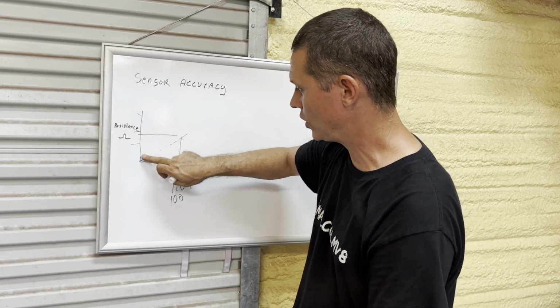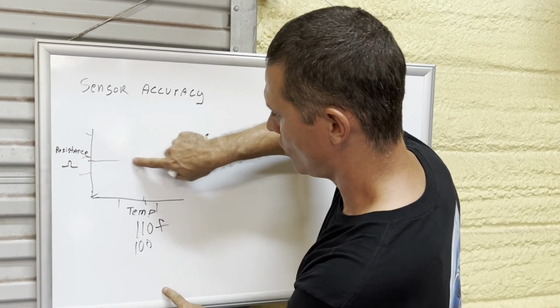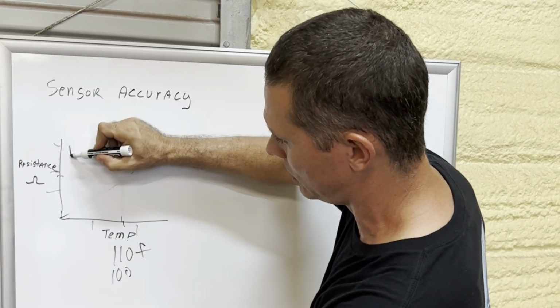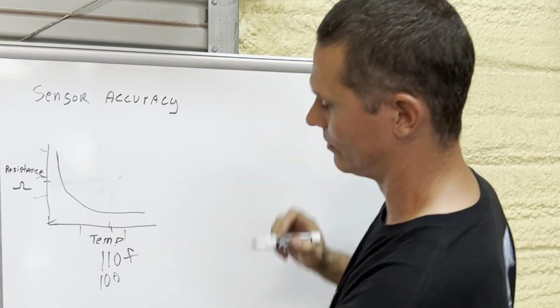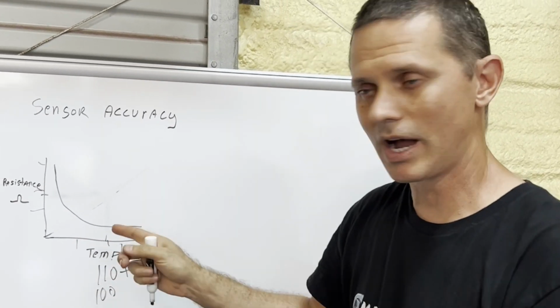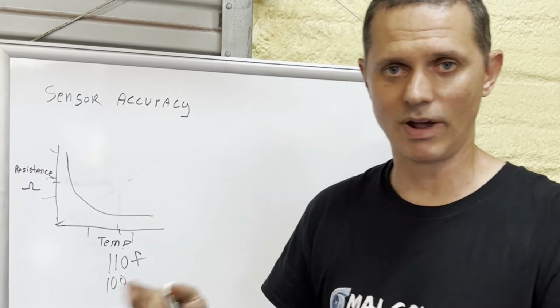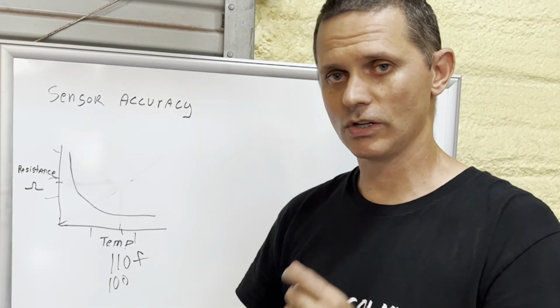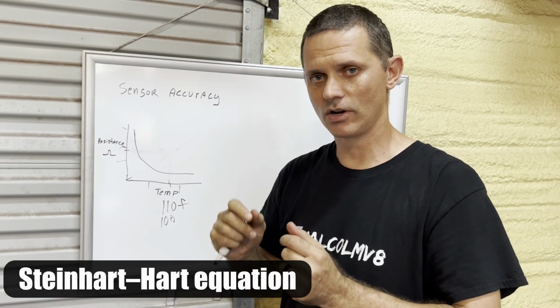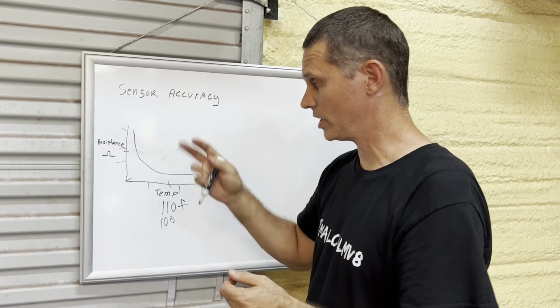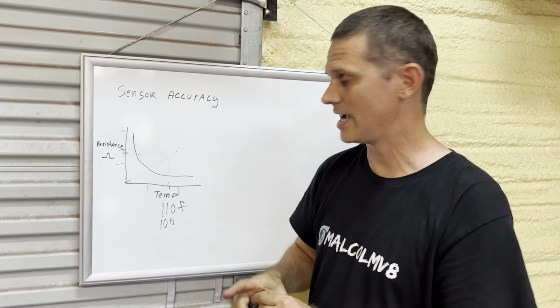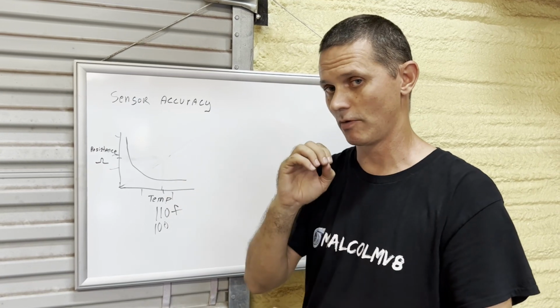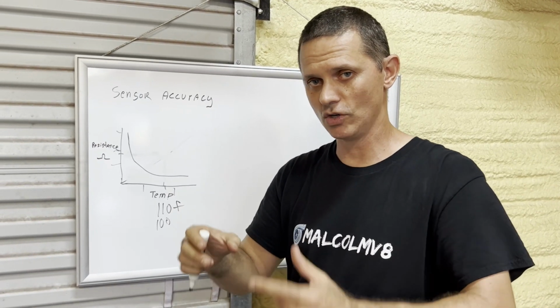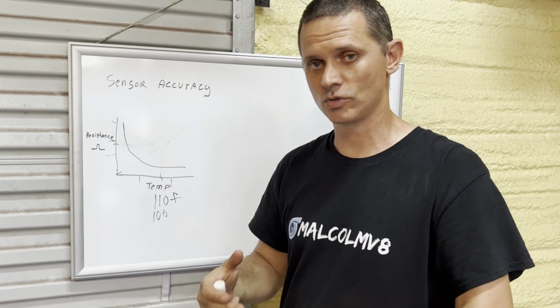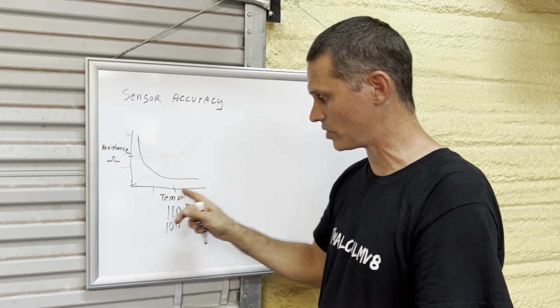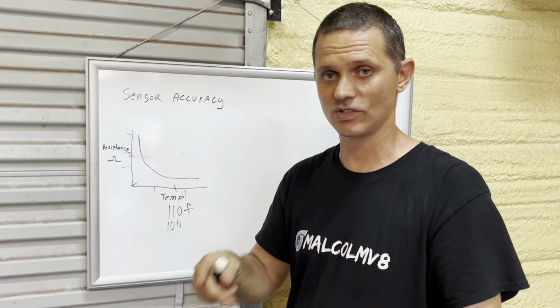So if you go look up an actual temperature sensor, what does its curve look like? It actually plots a curve that looks like that. Initially you think, oh wow, that's unreal, how do you write a formula to work with that? Well, you can look up a formula called the Steinhart-Hart equation. Some really smart guys came up with this in 1968, and they plotted this graph and wrote an equation that you can use in your code so that you can accurately predict where a temperature sensor's reading will be based on the resistance of the sensor.